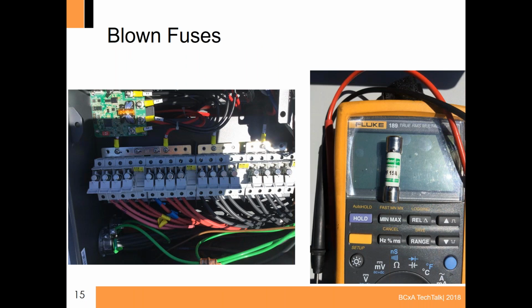And then blown fuses, again, just like a fuse in your house or a fuse box or circuit breaker, during the commissioning, we test for these blown fuses as well. And instead of just replacing the fuse and hoping that it doesn't blow, we work with the installers to identify, okay, well, why did the fuse blow? Usually a blown fuse would indicate some other trouble. So it's important, maybe we replace the fuse, but then we keep an eye on that string. We really want to investigate why that fuse blew and not just blindly replace it.